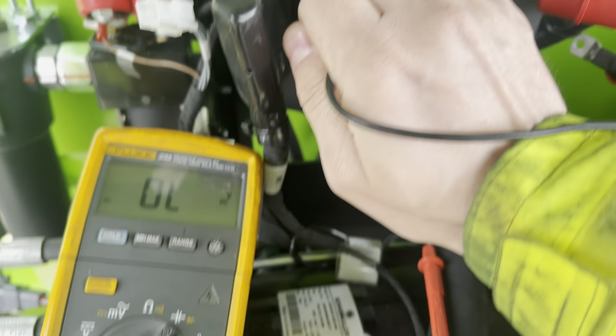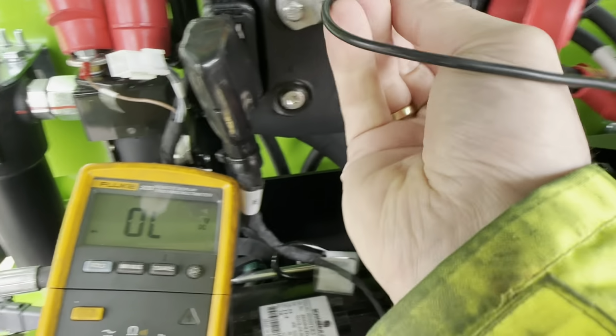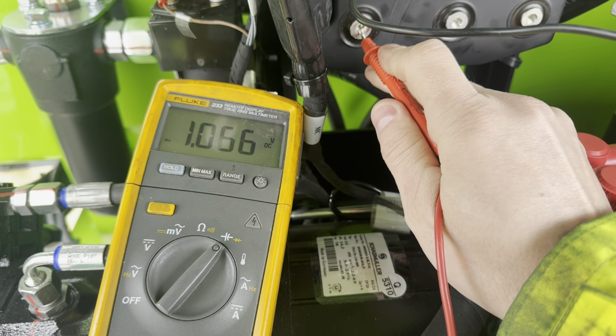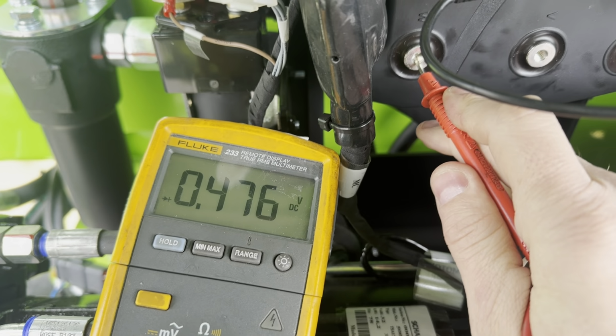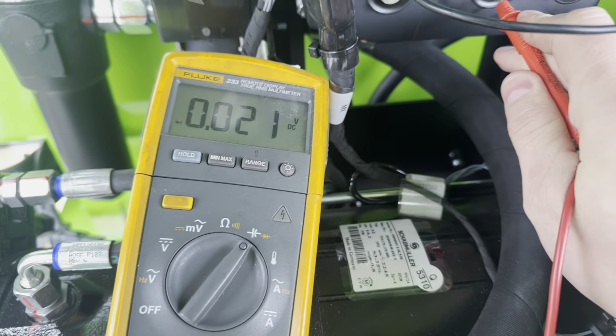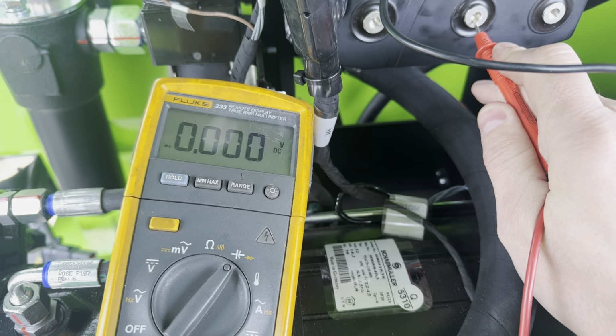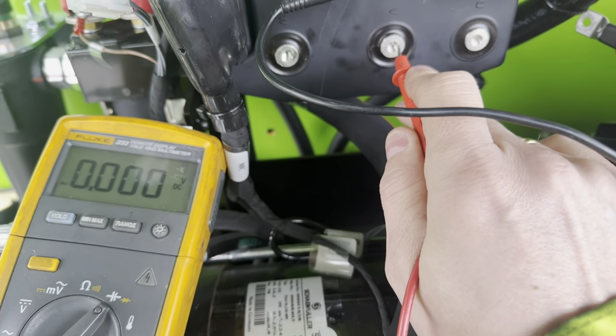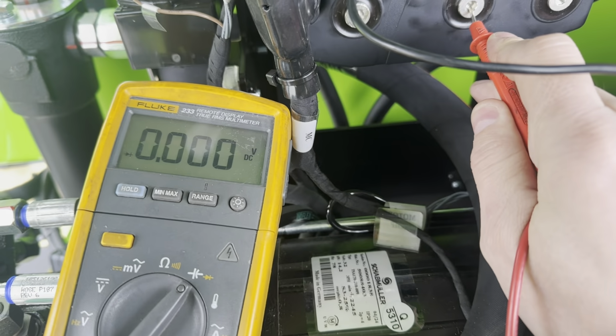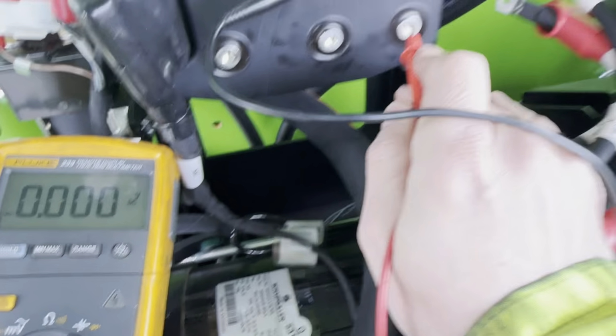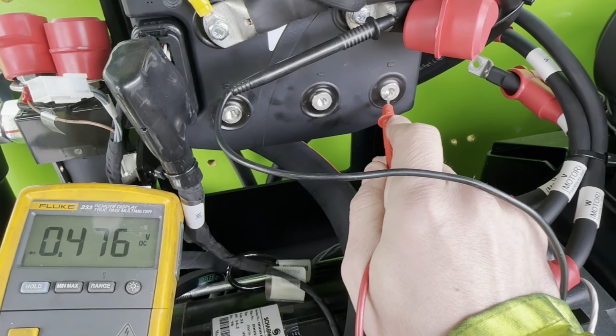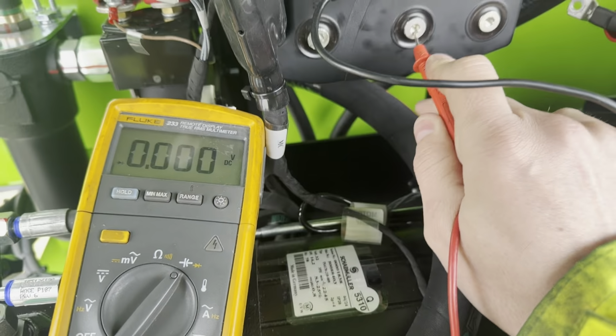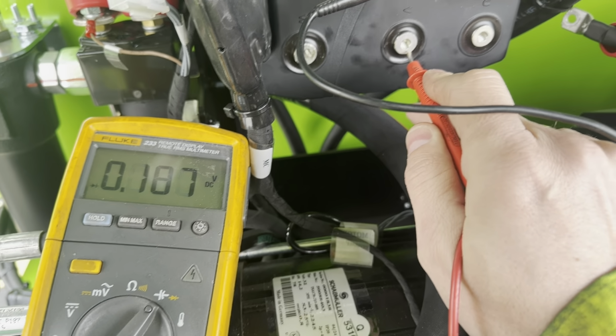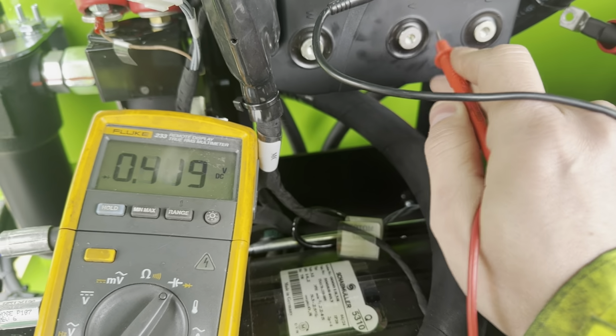And then if we go negative onto the positive here, so the black cable on the positive, B plus, we can do the same test with the positive going into a phase. So we have the same diode drop and the short circuit here. Okay, so now you know that this phase V is actually shorted to the positive. It's a completely short circuit, and phase U is correct. So if you're not too sure, do this check, and then you can be 100% sure that the controller is faulty.